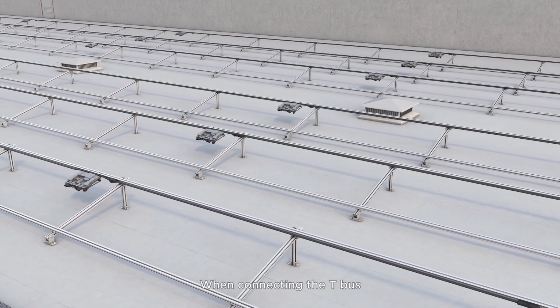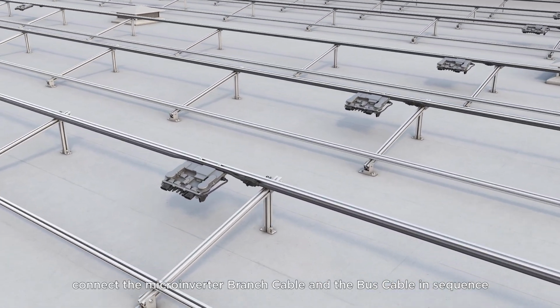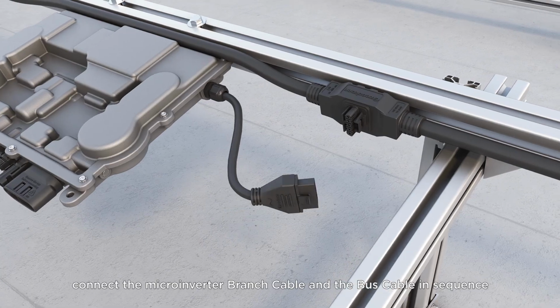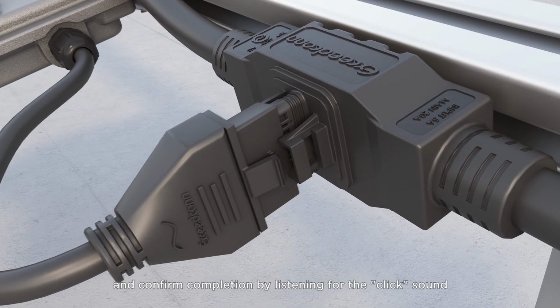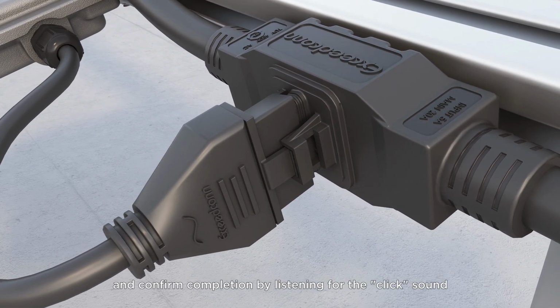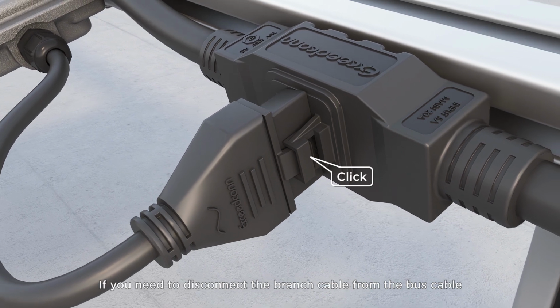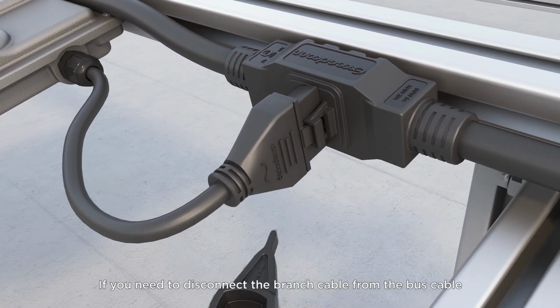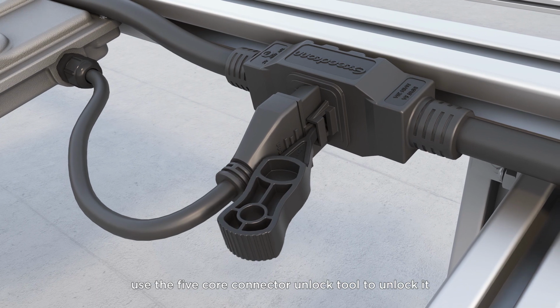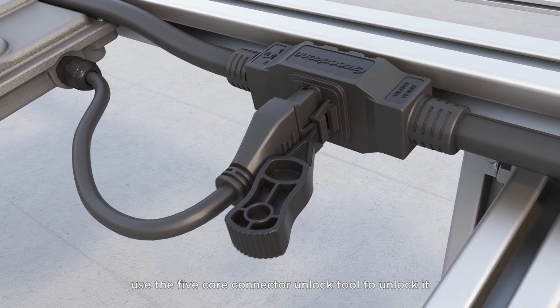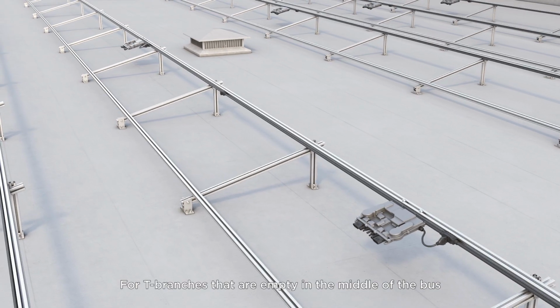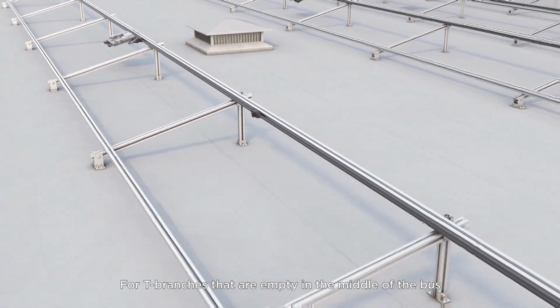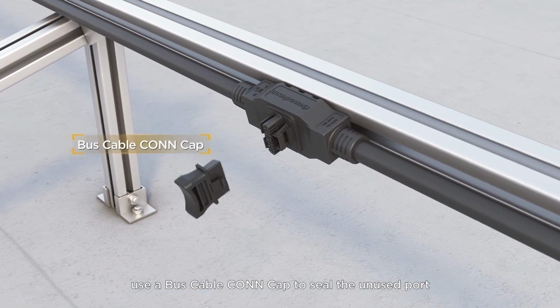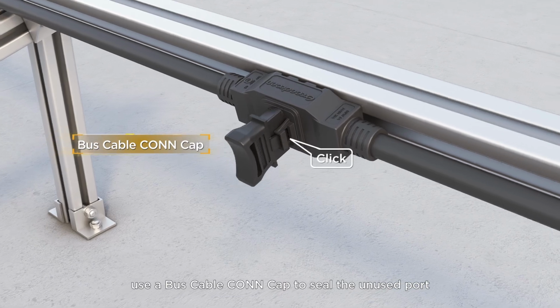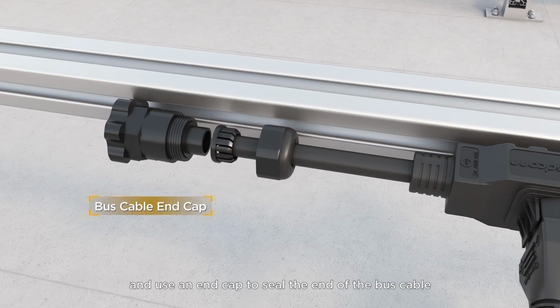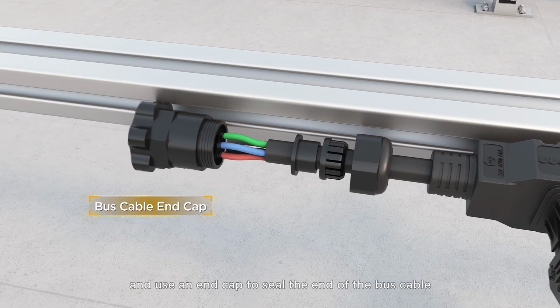When connecting the T-bus, connect the microinverter branch cable and the bus cable in sequence, and confirm completion by listening for the click sound. If you need to disconnect the branch cable from the bus cable, use the 5-core connector unlock tool to unlock it. For T branches that are empty in the middle of the bus, use a bus cable cap to seal the unused port, and use an end cap to seal the end of the bus cable.